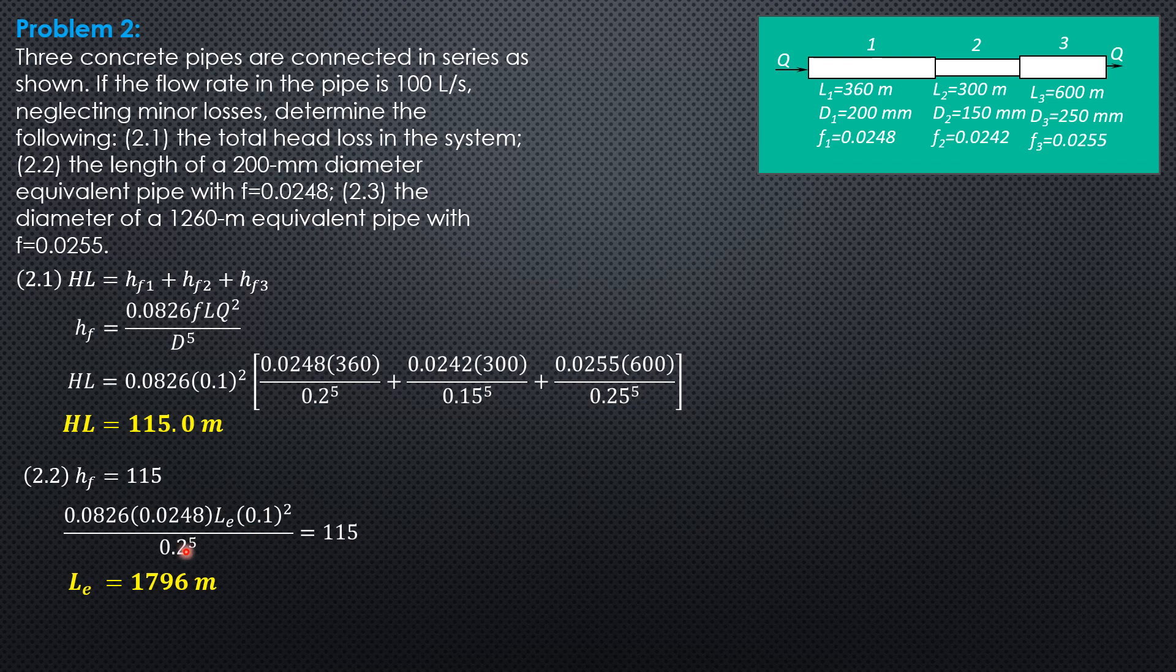but the diameter is to be, equivalent diameter is to be determined with friction factor 0.0255. So 0.0826 times 0.0255 times 1,260, 0.1 square over diameter equivalent to the fifth equals 115.